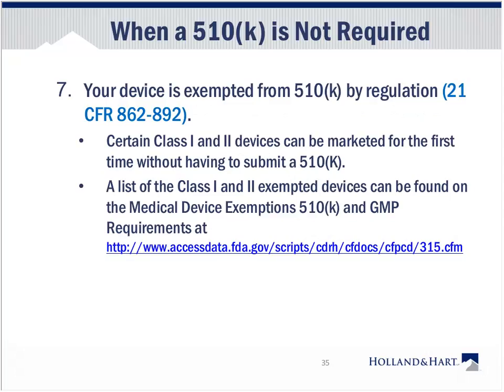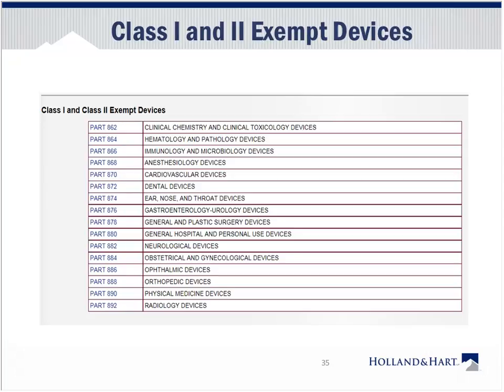And then again, we come back to devices exempted from 510K by regulation. So certain Class 1 and Class 2 devices can be marketed for the first time without having to submit a 510K. That is called an exempt device. For the exempt devices, there is a list of them. It's very big, and I've given you the site to it. The next slide contains the opening page of that, and you can see the subparts in the code. You can click on these when you're in the website, and you can start to parse out all of those devices which are exempted from pre-market notification.